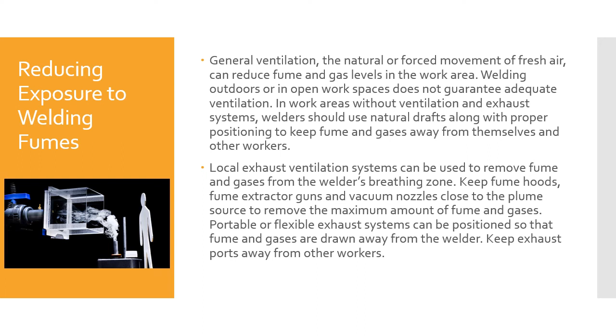Local exhaust ventilation systems can be used to remove fume and gases from the welder's breathing zone. Keep fume hoods, fume extractor guns, and vacuum nozzles close to the plume source to remove the maximum amount of fumes and gases. Portable or flexible exhaust systems can be positioned so that the fumes and gases are drawn away from the welder. Keep exhaust ports away from other workers.